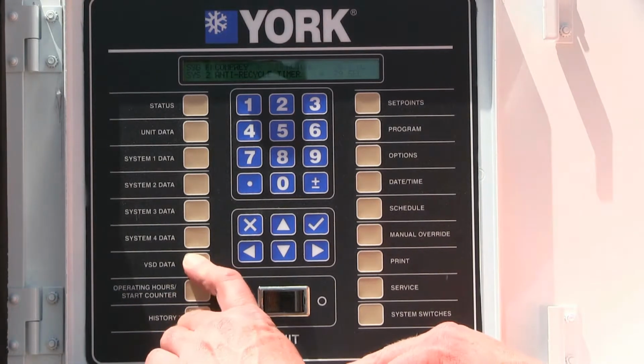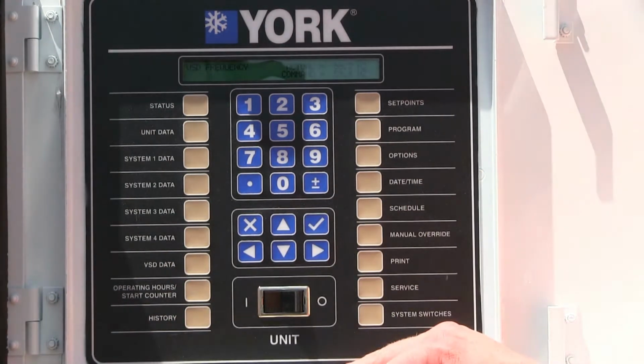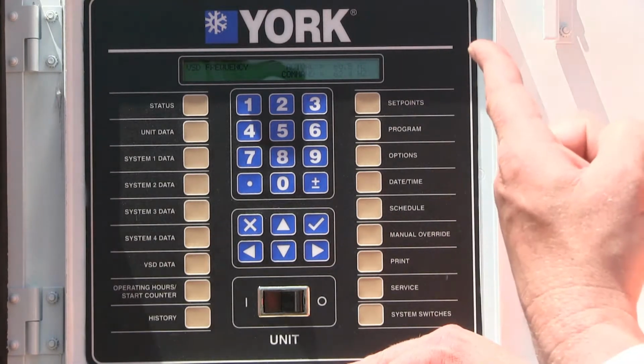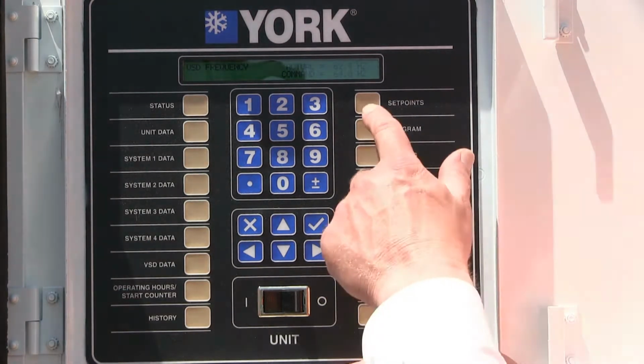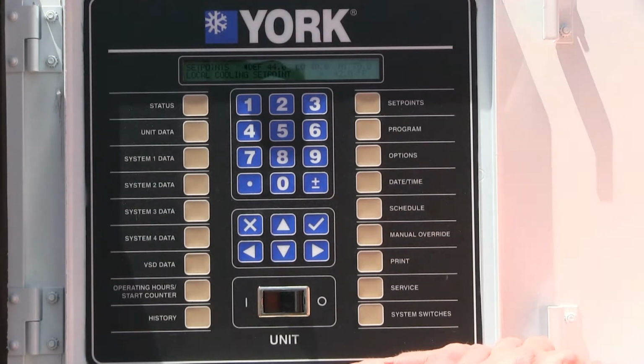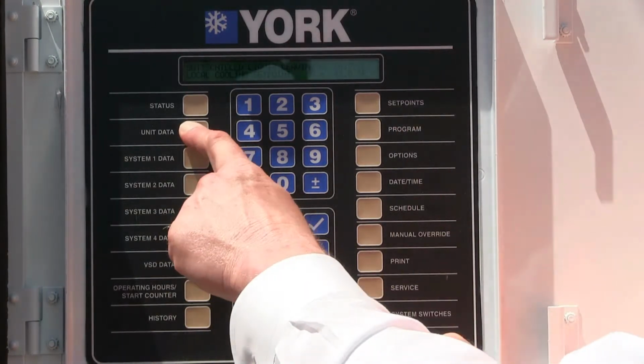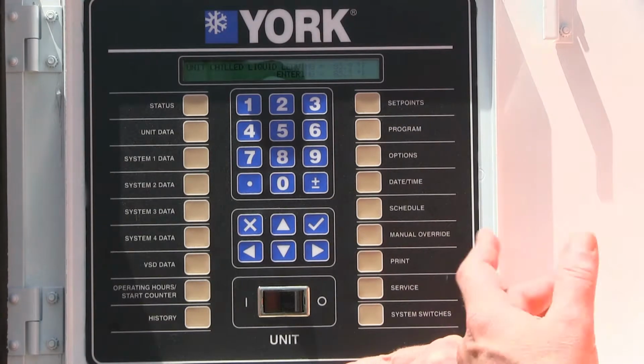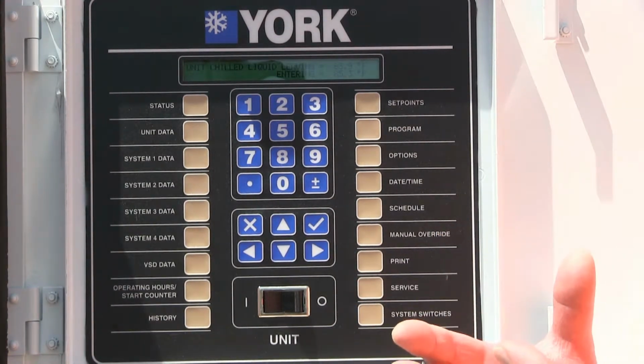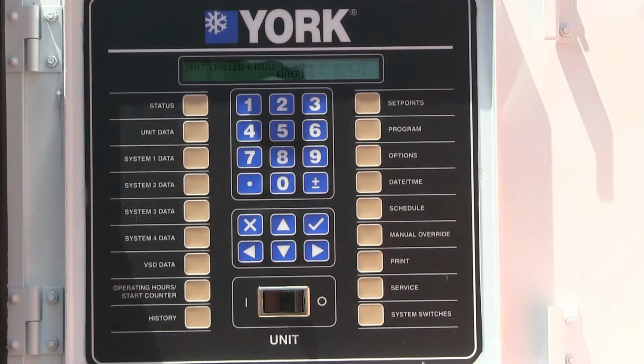You can always look at the variable speed data here. We're at 58 hertz, 59 hertz. It's commanding it. It's starting to go on. Our condenser fans are coming on now. Then there, our set point, again, it's still at 42 degrees. We go back to unit data. It's at 83, so we've already dropped about 1.5 degrees off our temperature, and we've barely started the machine.